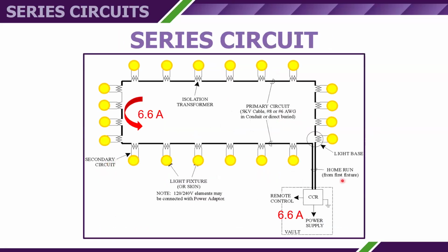So this, again, is your standard 6.6 amp airfield lighting series circuit. You have 6.6 amps that leaves the regulator, flows through the primary loop, and back to the regulator. All the current that leaves the regulator has to return to that regulator.